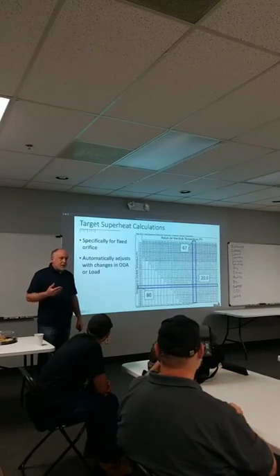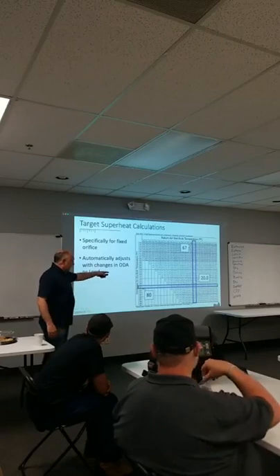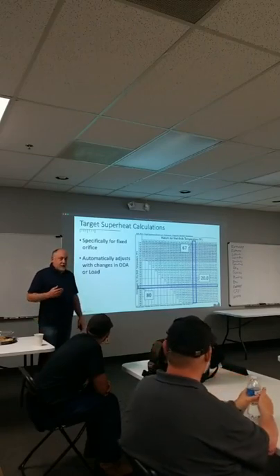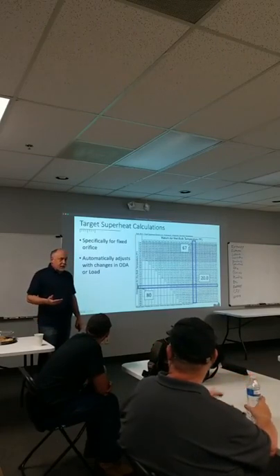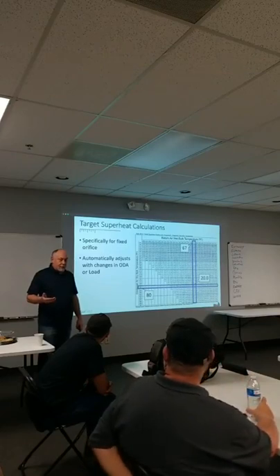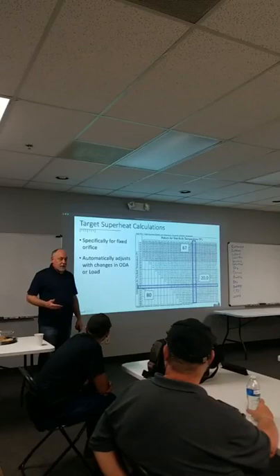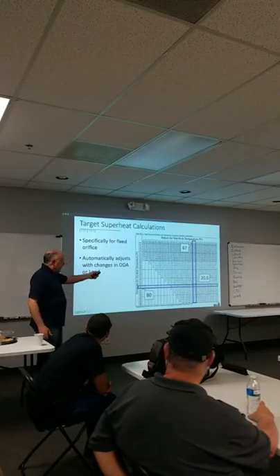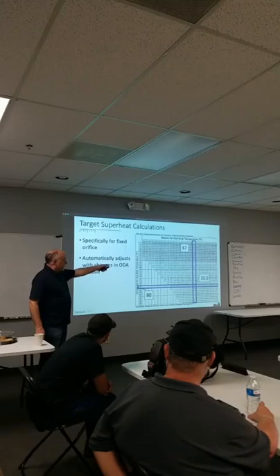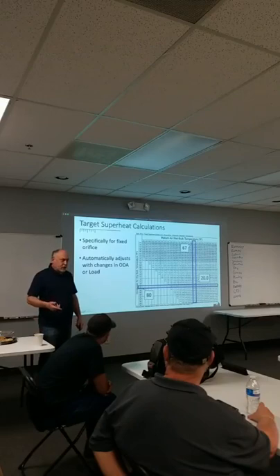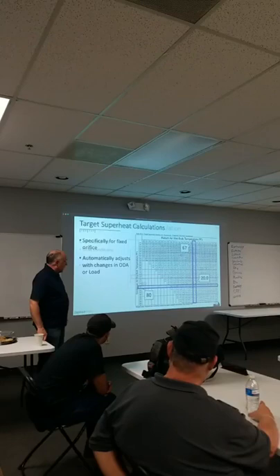A lot of these machines are very critically charged today. And believe it or not, when you get into things like microchannel, it could be that 1 degree of subcooling is the difference between the machine running properly and a machine losing a tremendous amount of efficiency and capacity. Ounces of gas can make a huge difference today. So Measurequick is running these calculations in the background in real time, constantly updating and showing you what the new target is supposed to be versus the measurement.